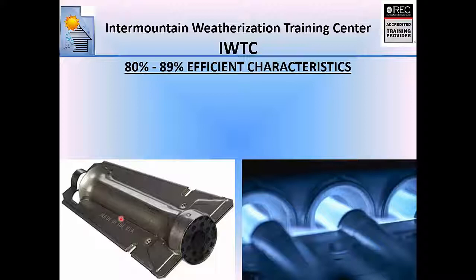Now, there were some very old first attempts at 80% efficient where they used a ribbon style burner with an inducer motor, but you won't run into too many of those out in the field. They did those for a year or two and then gave up on them, and everything 80% and higher switched over to these in-shot style burners. Okay, so that's another dead giveaway of what kind of efficiency you're dealing with.